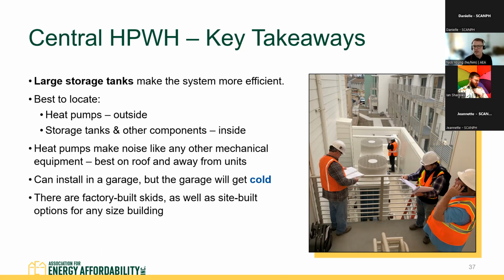Question: what is a factory built skid? I see Annette clarifying that it was residential. A factory built skid is basically where, in a factory, they mount the heat pumps on a platform, stick the tanks in place, put the recirculation pump, controls, and wiring together, pipe everything, and pre-build the whole system. Then it gets craned onto your roof, and all the contractor has to do is connect the electrical, hot water, cold water, recirculation, fill it with water, and turn it on. In theory, your on-site labor costs for a factory-built skid system could be much lower.